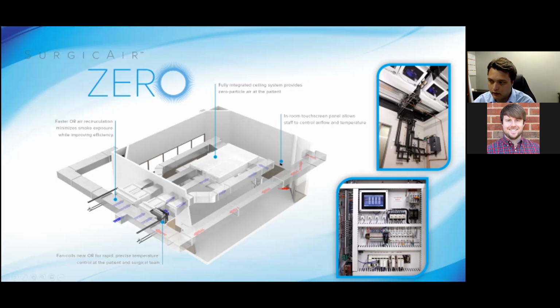Because we're recycling the air locally from that room, we actually don't even need the required 20 air changes from ASHRAE anymore from the house. We actually could get away with 10 or 12, or theoretically, if you have a DOAS unit or a high efficiency dehumidification system, you could get away with giving us the 4 air changes from outside. And we've had some studies that show that this actually can lower the energy requirements for a surgical suite by up to 30%, simply by putting the system in there, and you get that added benefit of 0 particles.